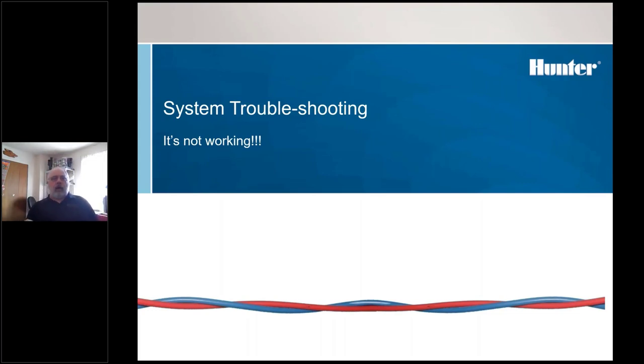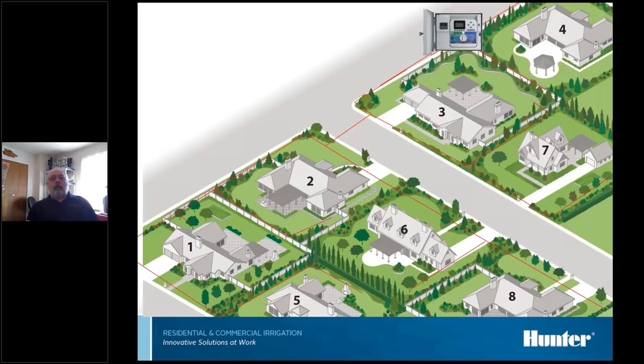Okay, so now we'll go to actual troubleshooting. I encourage everybody to have a process that you use. I certainly do. I go through pretty much the same steps no matter what. And the first thing I do is I go to the controller and see what the controller can tell me. They vary a bit. The ACC controller's got all kinds of alarm logs and stuff in them. They'll tell you all kinds of information about what's going on, what's been going on. Go find out what you can find out of the controller before you go any further.